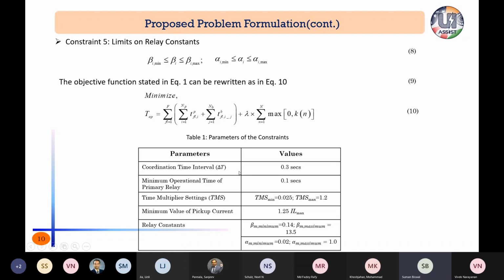For example, coordination time interval 0.3, primary relay operational time 0.1 second or 100 milliseconds. We have explained the time multiplier setting bounds and also the pickup current constraints. We have taken the pickup current as 1.25 times IL max, because this pickup current is decided on the basis of the normal load current.